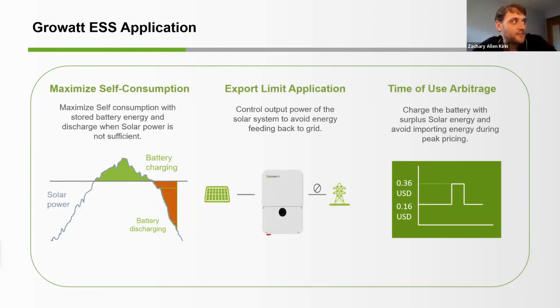The MIN also has zero export or export limitation applications. So when zero export features are being used, the battery is charged with the clipped solar energy that normally would have been exported to the grid. For this type of system, you will also need to procure a Growatt smart meter. This is to make sure the inverter is sensing exactly how much energy it needs to produce to supply to the customer's load, and then not produce any more energy to export to the grid. So we're trying to avoid feeding any energy back to the grid, and the Growatt smart meter also gives your customers access to their consumption data.